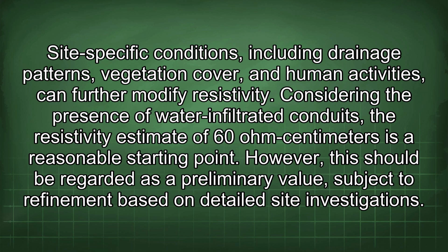Considering the presence of water-infiltrated conduits, the resistivity estimate of 60 ohm-centimeters is a reasonable starting point. However, this should be regarded as a preliminary value, subject to refinement based on detailed site investigations.